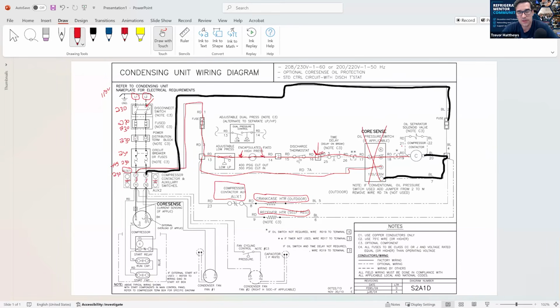A fan's out. That's basic. Your condenser fan motor, you can see it's out. You can take your compressor's leads, short it, and then ohm it out, with the power off and all the wires off properly, safely, and locked out. And then you check it. Then, okay, it's grounded, or it's a short, or the motor's shorted.